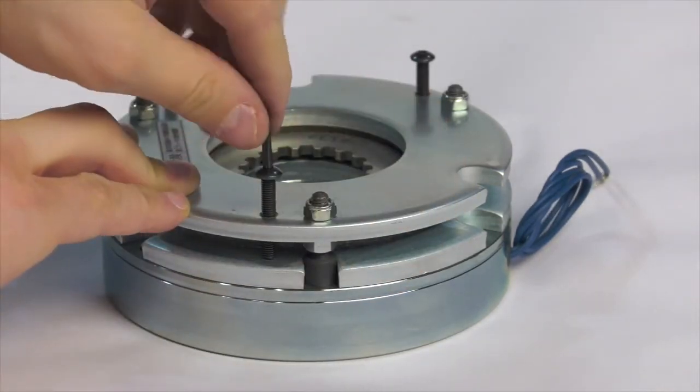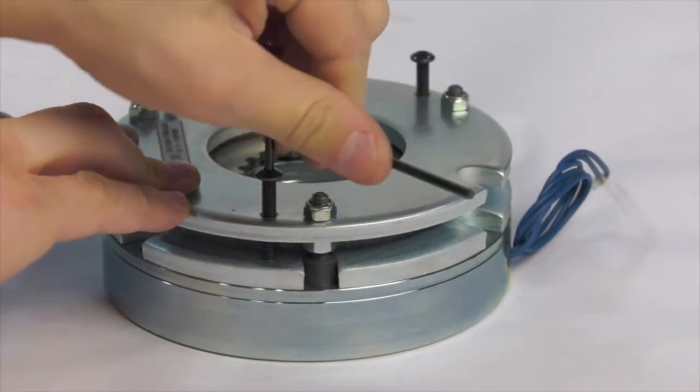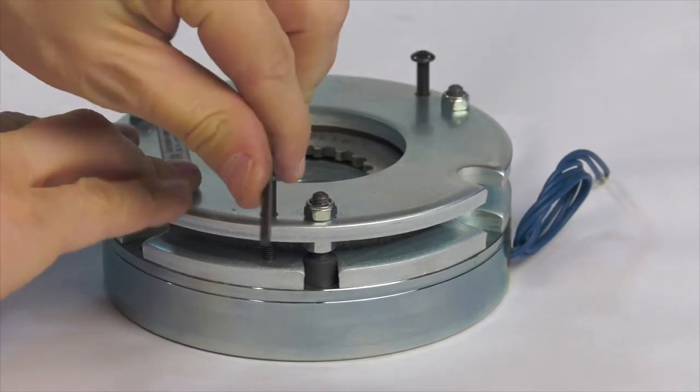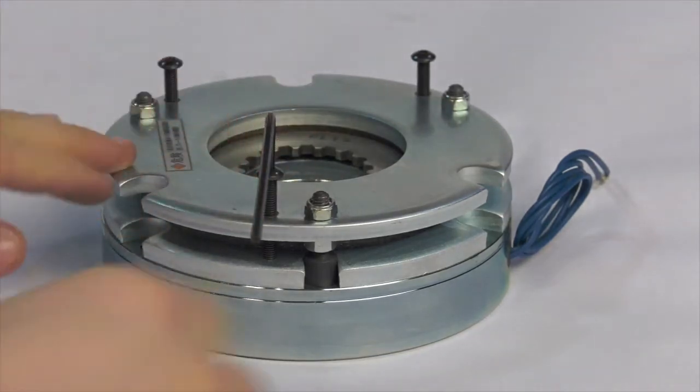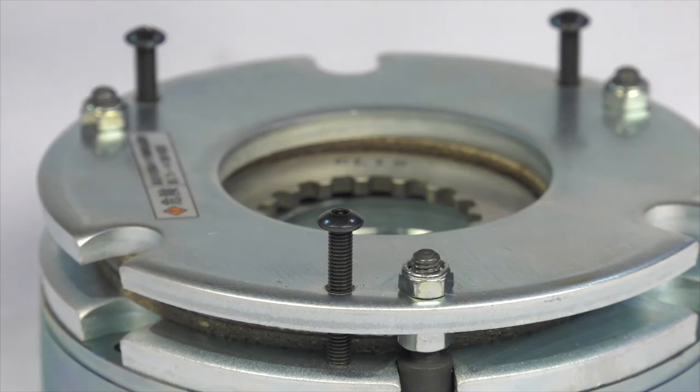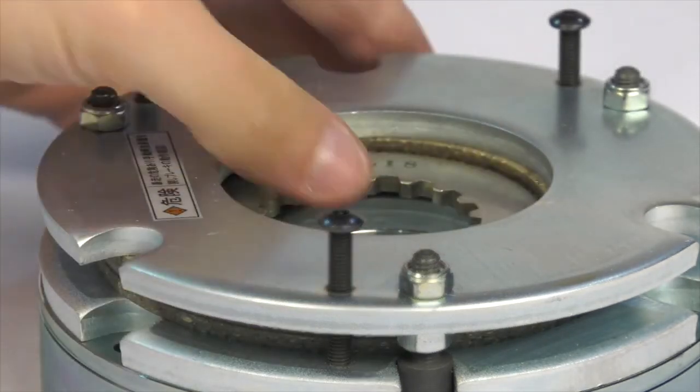Once the screw touches the armature, the brake will release with approximately another 90 degree turn. Take care not to over tighten the screw beyond the point where the armature contacts the field or this will damage the cover plate.